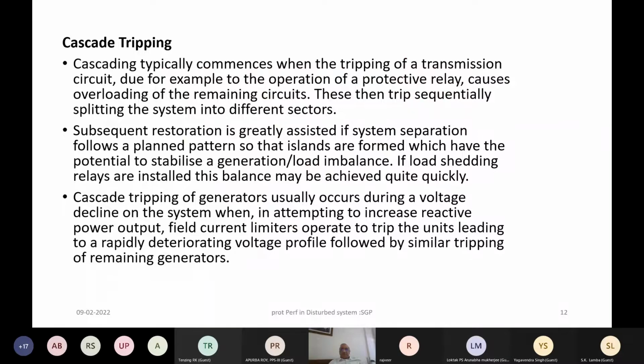Once this power swing phenomena takes place, then as we experience in various disturbances in India, cascade tripping takes place because some distance protection will respond to power swing or the voltage collapse phenomena. Voltage collapse phenomena basically results in low voltage accompanied by very high current, which is mainly reactive current. And this low voltage and high current will result in encroachment into the impedance setting of the distance relay, mainly zone 3, which is very close to the load point of the line. Longer lines are more susceptible to such a phenomenon.